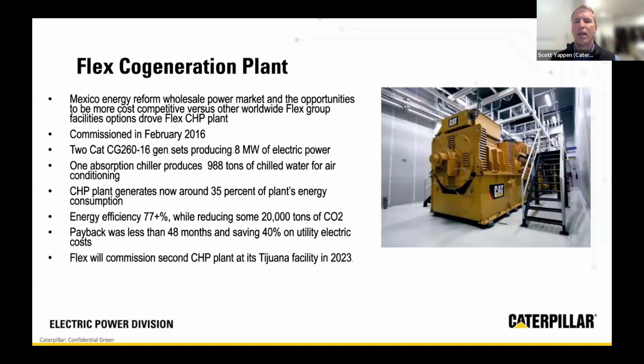These generate with a frequency of 60 hertz in Mexico, so for some of you outside, in the rest of the world with 50 hertz, these are 60 hertz. These are very low speed RPM engines, rotating at a speed of 900 RPM, with a heat rate of less than 7,800 BTUs of fuel per electric kilowatt generated, per engine.